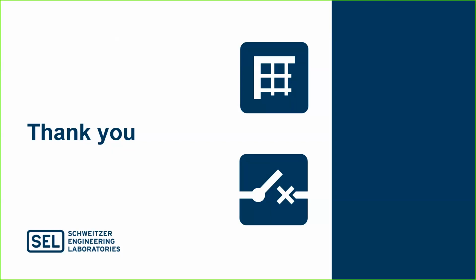Mitigation steps would be you can go into FLISR or send it a DNP control saying, hey, treat that device as out of service closed or out of service open, at which point FLISR will unblock itself and will be perfectly happy to treat that device as a bump in the wire or as an unresolvable air gap, and it'll work around it. We have been asked by multiple people to add a setting to FLISR that is, if you lose comms with a device, treat it as if it were in last known state. That's something we're looking very closely at, and something we will probably add.